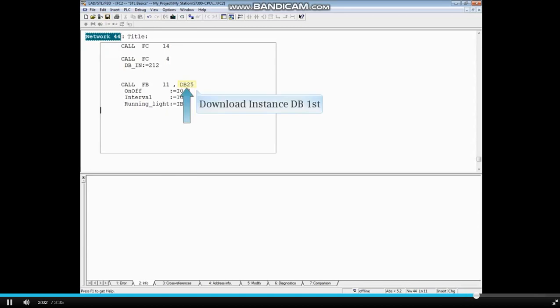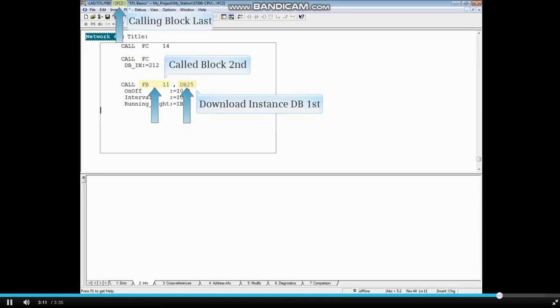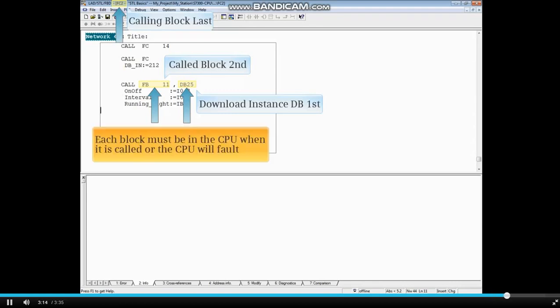After making a call to an FB, don't forget to download the associated data block first, then the FB that is called, then the block containing the FB call. Each block must be in the CPU when it is called, or the CPU will fault.